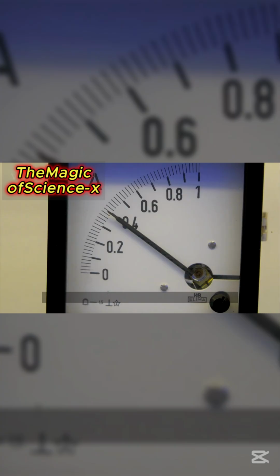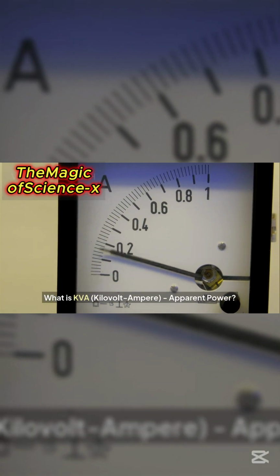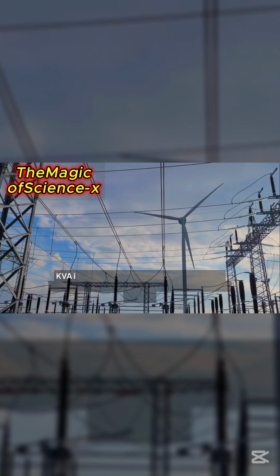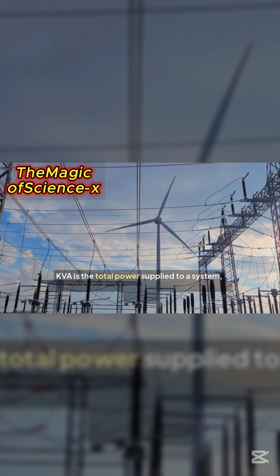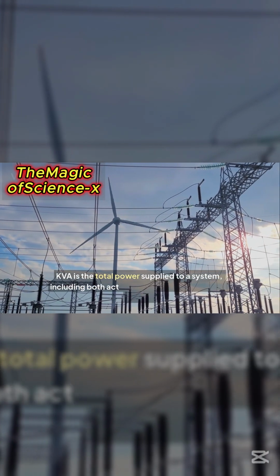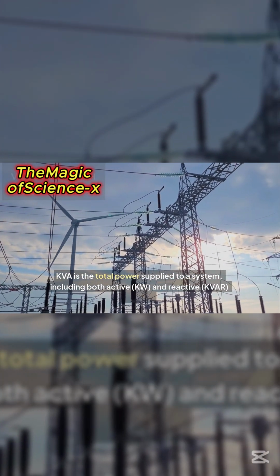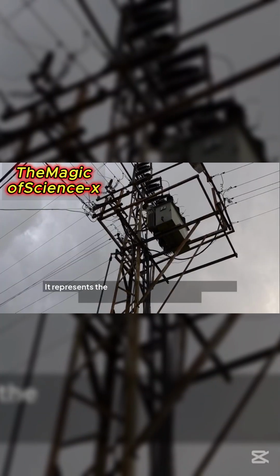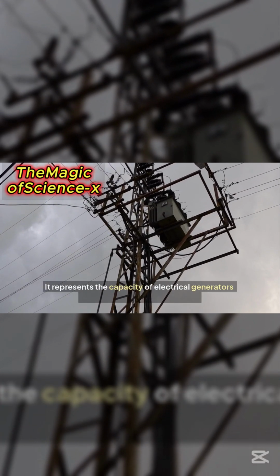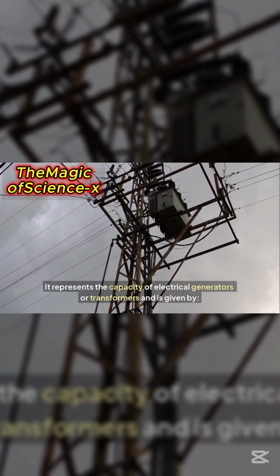It is measured by the equation P (KW) equals voltage times current times power factor. What is KVA? Kilovolt ampere, apparent power. KVA is the total power supplied to a system, including both active (KW) and reactive (KVAR) power. It represents the capacity of electrical generators or transformers and is given by S (KVA) equals voltage times current.